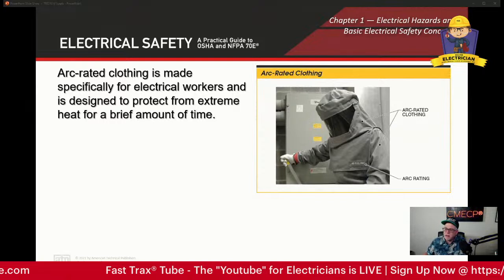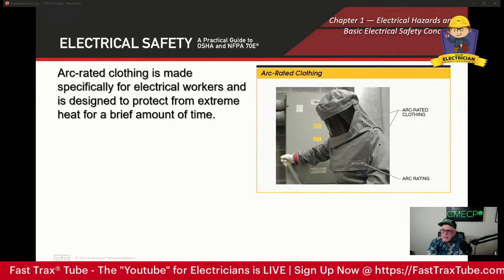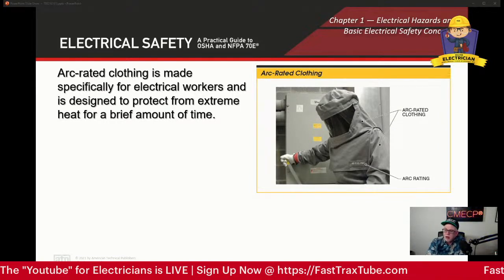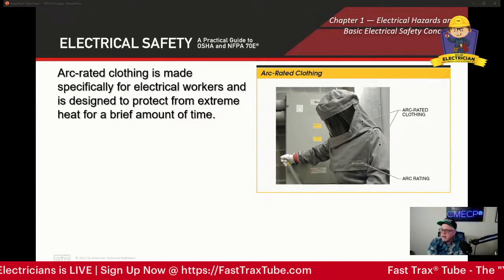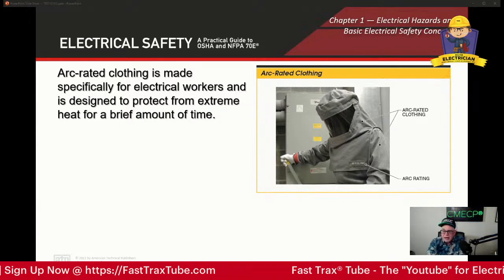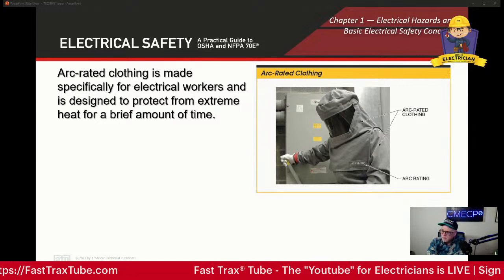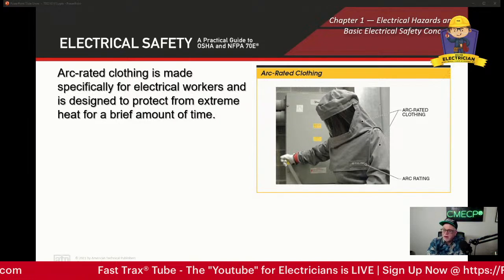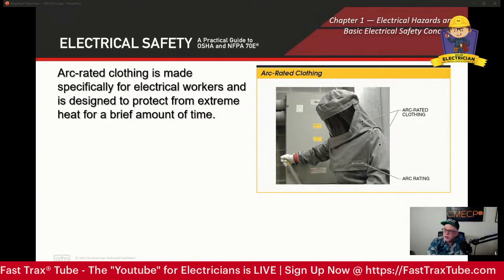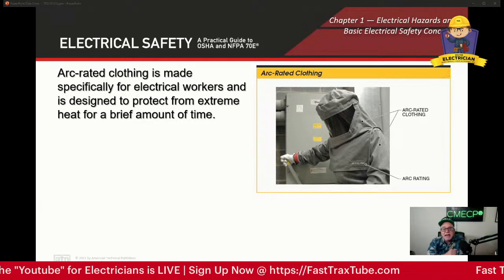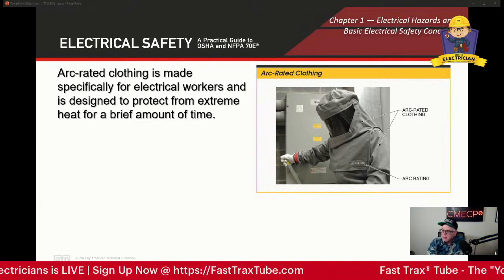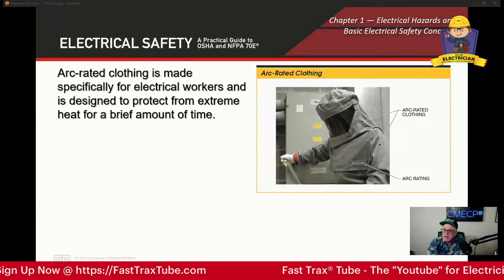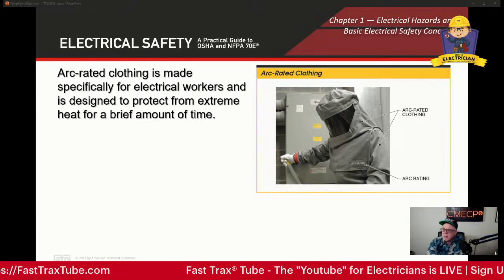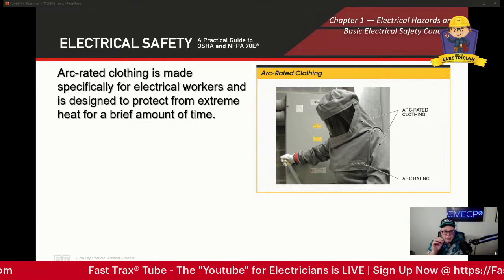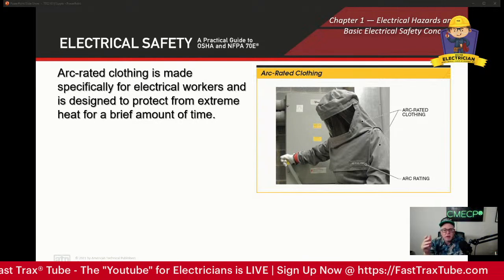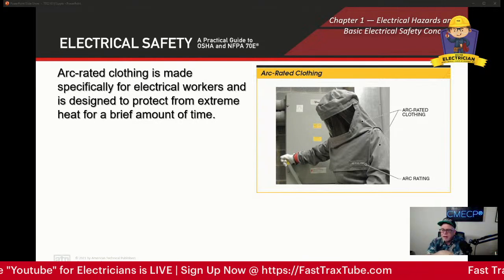The intent of NFPA 70E is for electrical workers to wear clothing specifically designed and rated for its use, i.e. arc ratings, as opposed to firefighters, steel workers, and other workers who must wear flame-retardant FR clothing. This is because the heat created by an arc flash is extreme, but it's only momentary - not long-term exposure like a fireman would face.